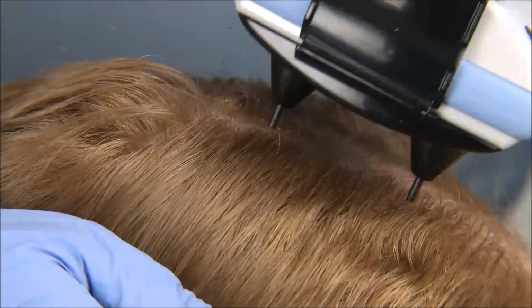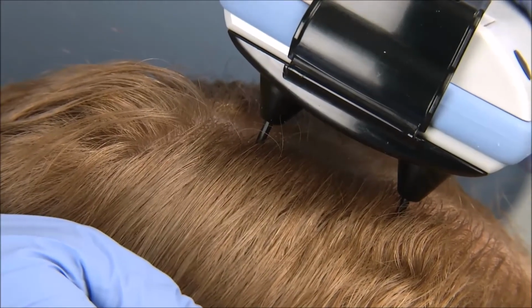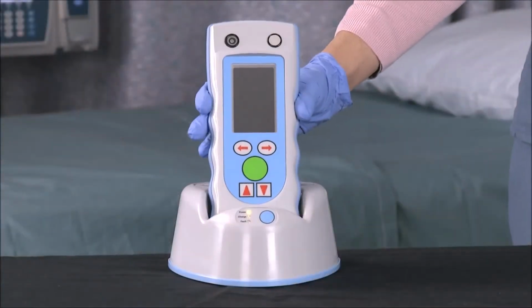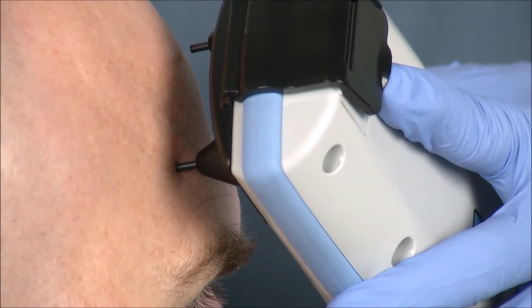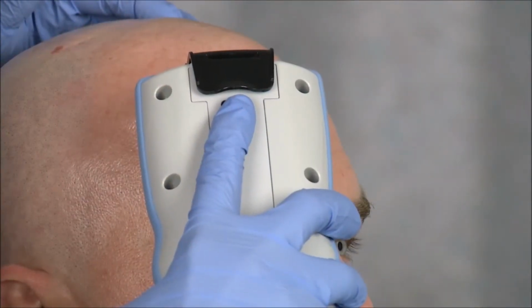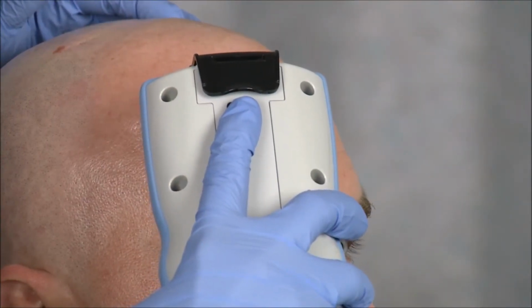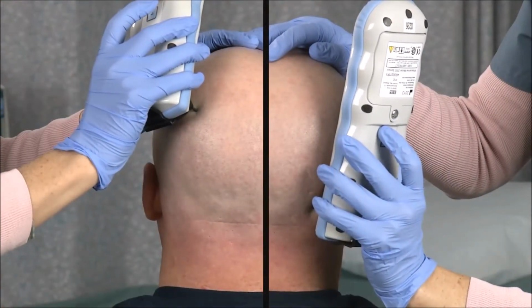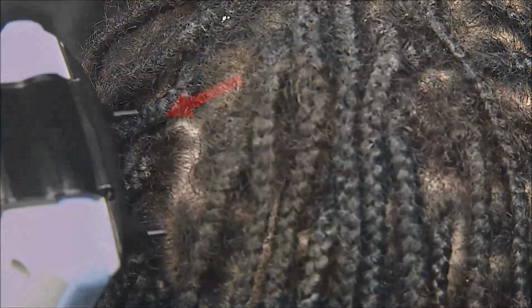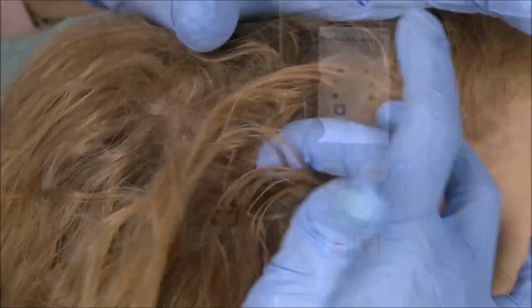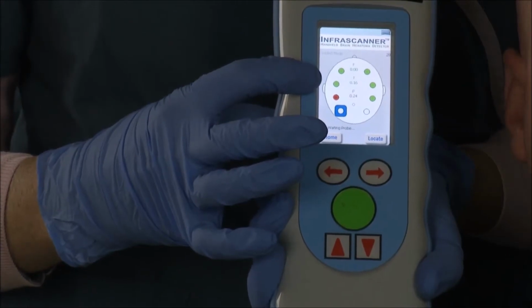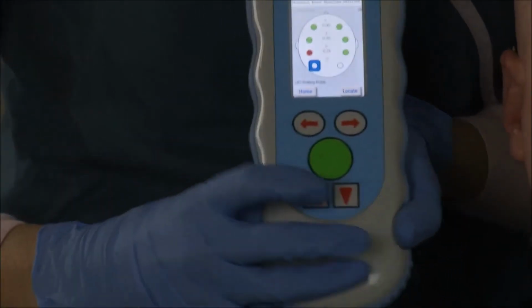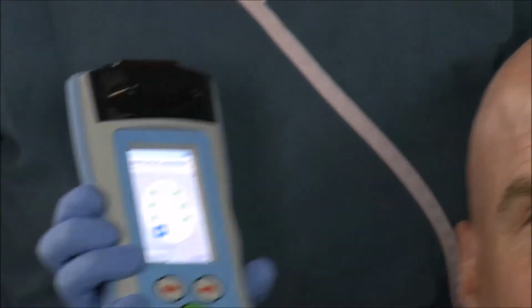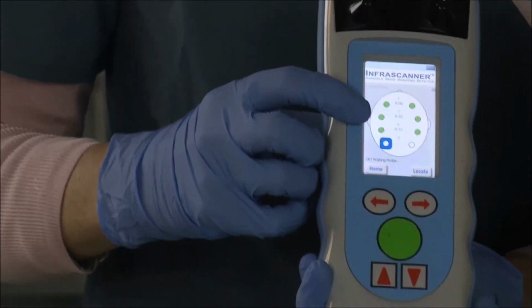The most common mistakes that can cause error codes are low battery, non-uniform pressure, pressing and holding the measurement buttons when trying to initiate a measurement, non-symmetrical location for readings, hair under the fiber optic tips, too much overhead light, hair gel or hair weaves. And remember, whenever you get a hematoma positive or red danger reading, re-scan up to 2 additional times to verify.